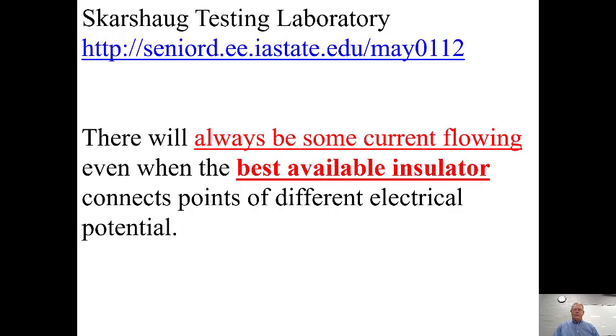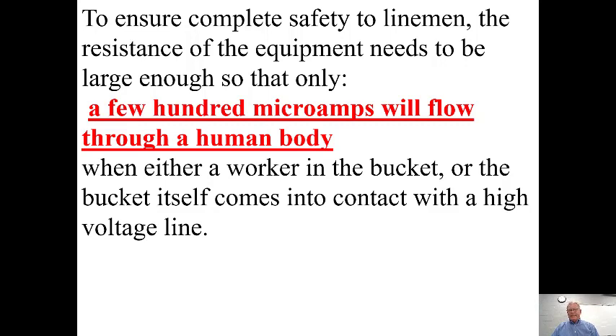But this testing laboratory says there will always be some current flowing, even when the best available insulator connects points of different electrical potential. So what's that telling us? There's no perfect insulator. This is also important, coming to a quiz, midterm, final near you: there is no perfect insulator. Those porcelain insulators on all the highline poles, they do pass some current, okay? To ensure complete safety to linemen, the resistance of the equipment needs to be large enough so that only a few hundred microamps will flow through a human body when either a worker in the bucket or the bucket itself comes into contact with a high voltage line.